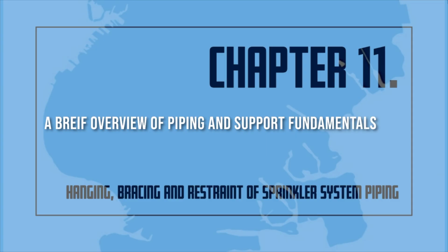The minimum size hanger rods are required as follows. For up to and including 4-inch pipe, a 3/8 inch rod is required. For 5, 6, and 8-inch pipe, a 1/2 inch rod is required. For 10 and 12-inch pipe, a 5/8 inch rod is required.